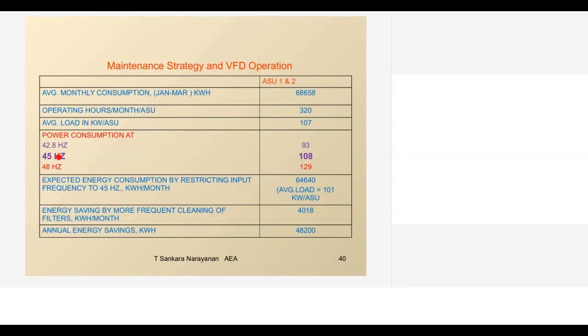Whenever frequency increases, with purely cleaned filters you are getting only 93 kilowatt. When slowly choke up is there, it is going up to 129. Then we gave a guideline: whenever the frequency of ASU operation is 45 cycles, you take it for filter cleaning. So this is only an operational improvement. What we are telling is, many a time industry is putting a large number of VFDs, but the VFD is operated closer to the supply frequency, 49.2, 49.3. That means either the application is not good or the application is not requiring a VFD. So we have to review, whenever we are having a VFD, what is the real saving margin we got.